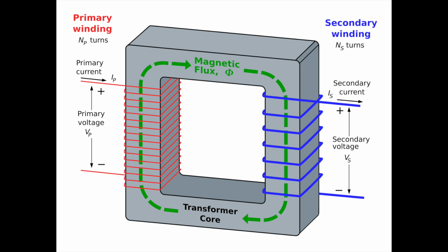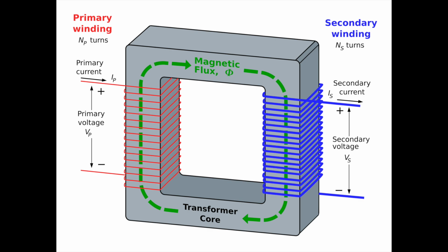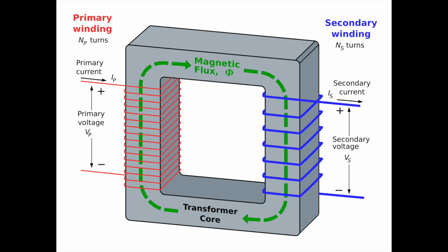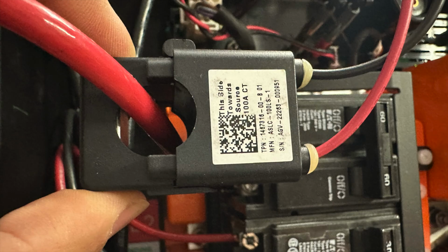If the secondary winding has more turns of wire than the primary winding, the transformer steps up the voltage, and in order to keep the same amount of power, the current is reduced. If the secondary winding has fewer turns than the primary, the transformer steps down the voltage and the current increases. So a CT is just a step-up transformer that takes a large current that's difficult to measure and transforms it into a lower current that can be measured.